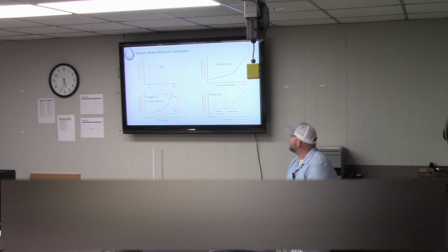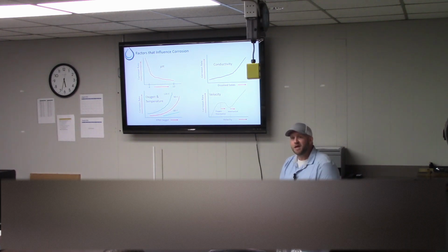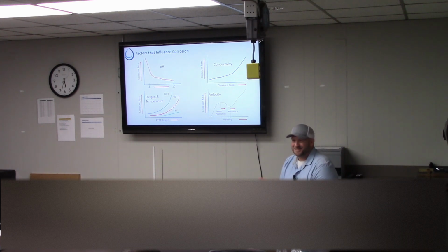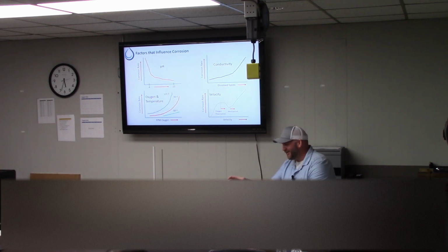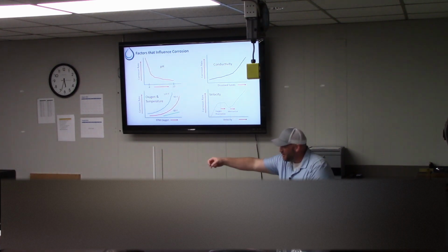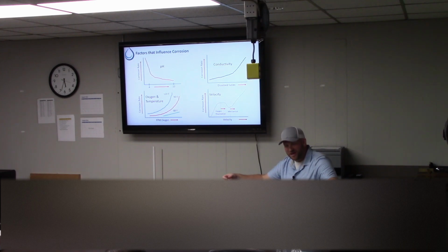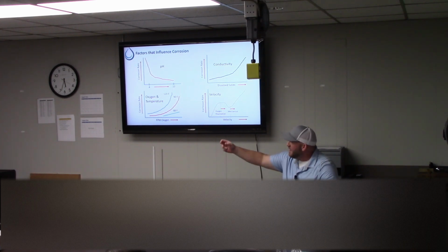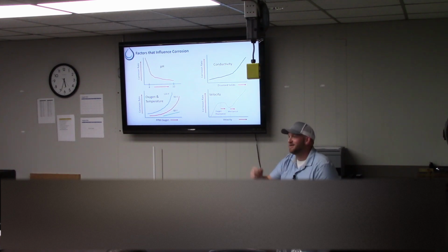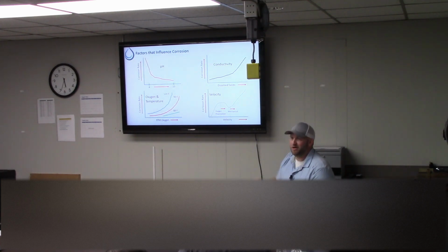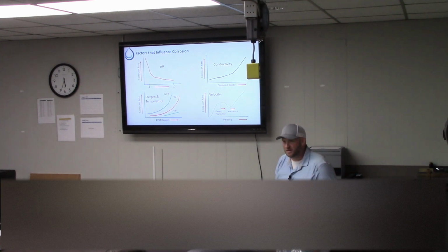Conductivity is the other thing that will influence corrosion rates upward. As we increase dissolved solids, corrosion potential increases. Did anybody do that science experiment—I know I did, it's fun—where you take a tank of pure water, put the light bulb over here, drop the cord in that end, and it doesn't light up. Put a little salt in it, and all of a sudden it lights up. This is that principle. If you have pure water, it's not conductive. It will not conduct electricity.